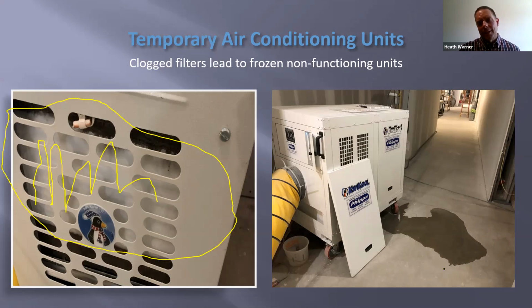The picture on the right, obviously very similar, frozen coil, it's being thawed out. But this is actually damage that occurs, and when I say damage, it's inefficiencies, when you're trying to overtax an air conditioner unit. This particular job really needed about 30 tons of air conditioning, which is really expensive. I'm not saying it's not, but just volume wise, it needed 30 tons of air conditioning. Contractor decided that they would try to roll the dice and go with a little bit lower output. They went with about 15 tons of output, or half of what was actually needed. All of the temporary AC units were continuing to freeze up for the entire job. And the reason was they were operating 24/7. The units were never cycling. So the coil sets not only couldn't breathe, they never could cool off to the point where they could actually be effective and clean themselves. That's very similar to what's going on with your permanent system if you're using it during construction phase.